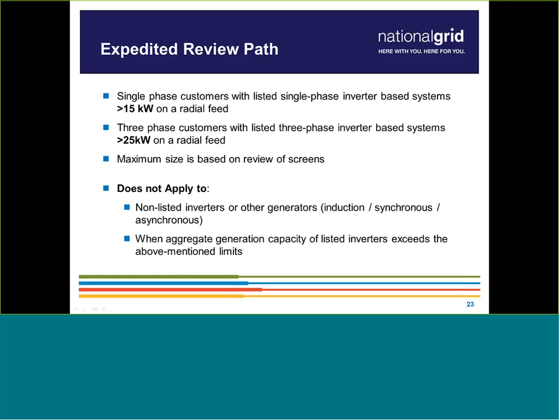Here's the time frame involved: 3 days to acknowledge the application, 10 days to say it's complete, and about 25 days to review the screening to make sure it's adequate. After that, if further review is needed, 20 days for a second review. Then there's 10 days to send the agreement, once you've said you're okay with the supplemental review results or screening results, we draft up the service agreement. So the total time frame is 45 to 65 days, depending on whether supplemental review is needed.